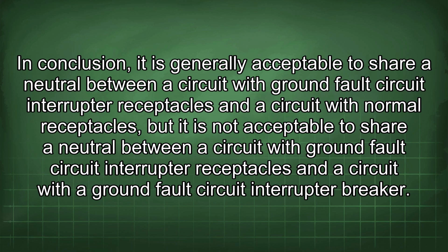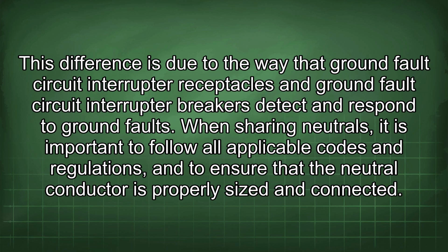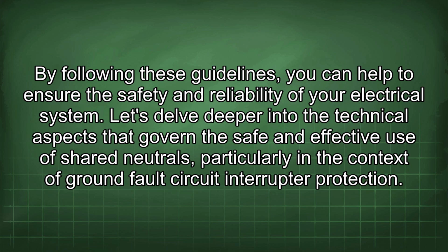In conclusion, it is generally acceptable to share a neutral between a circuit with ground fault circuit interrupter receptacles and a circuit with normal receptacles, but it is not acceptable to share a neutral between a circuit with ground fault circuit interrupter receptacles and a circuit with a ground fault circuit interrupter breaker. This difference is due to the way that ground fault circuit interrupter receptacles and ground fault circuit interrupter breakers detect and respond to ground faults. When sharing neutrals, it is important to follow all applicable codes and regulations and to ensure that the neutral conductor is properly sized and connected. By following these guidelines, you can help to ensure the safety and reliability of your electrical system.